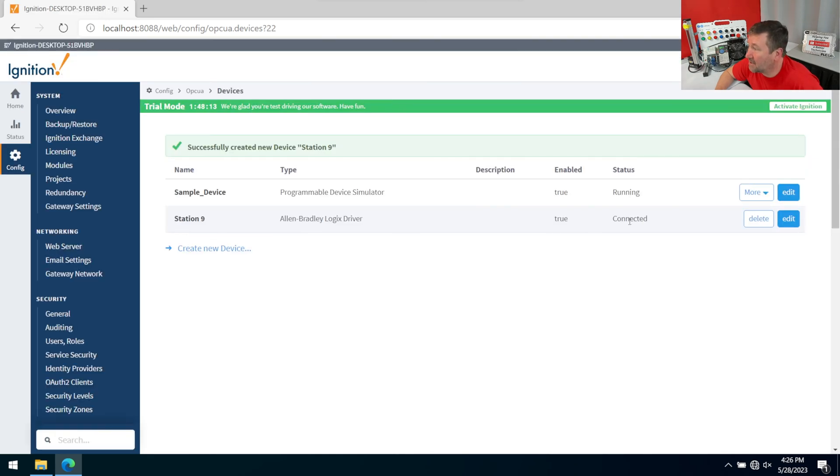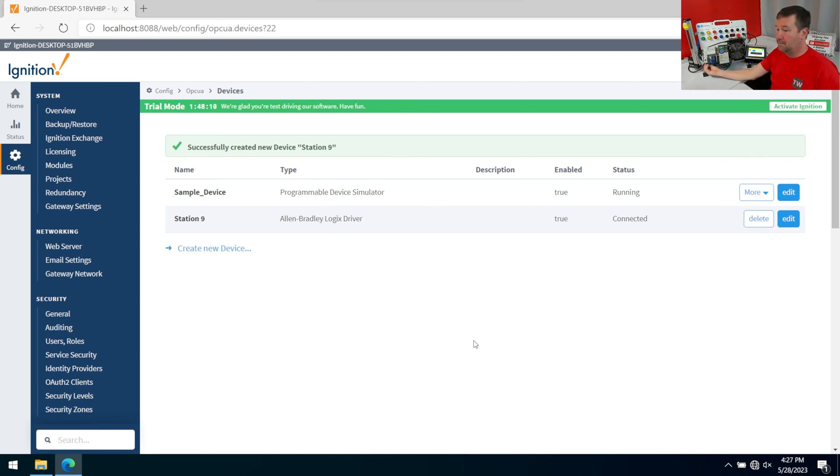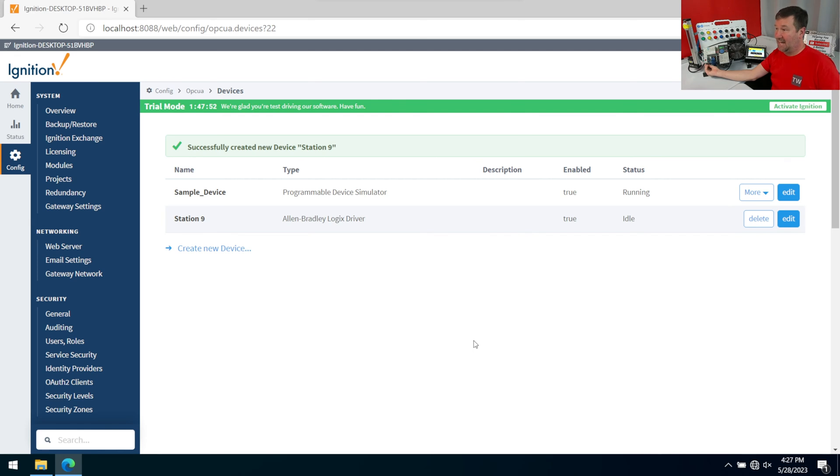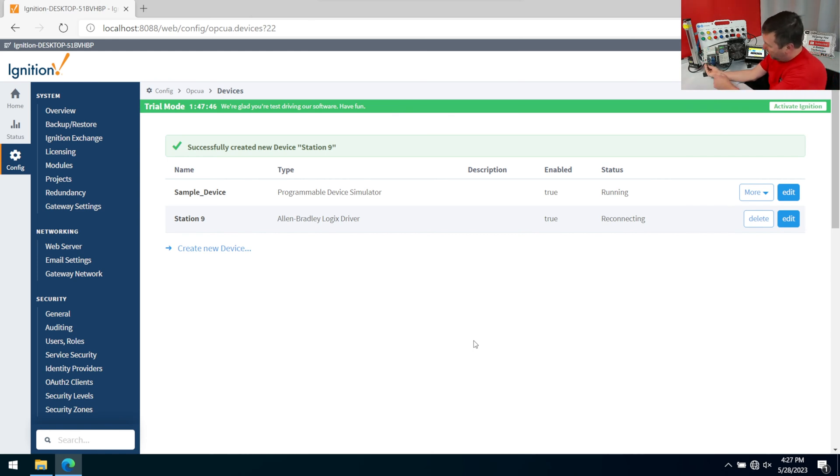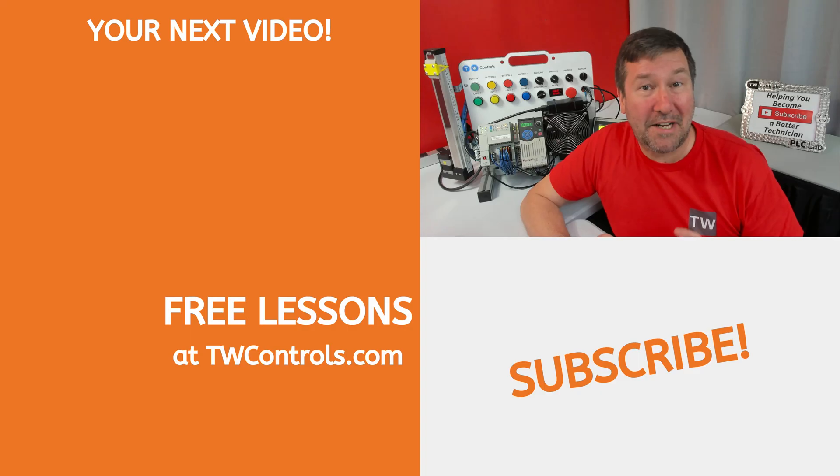We can tell that it's working because it says connected here. If I unplug my CompactLogix PLC, then it's going to switch to idle. So if yours does not say connected there, then check your IP address and the driver type that you selected.